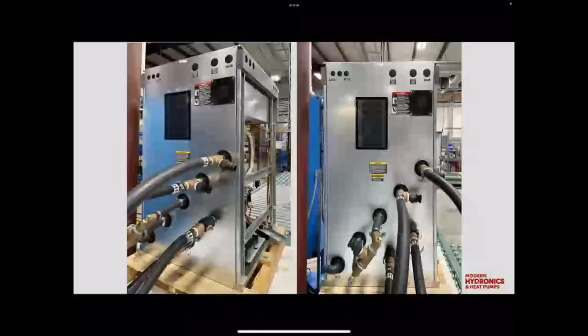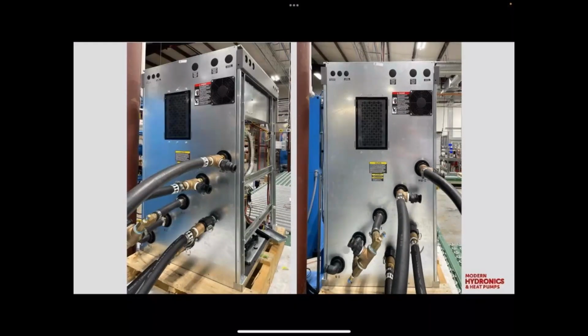So as we get in here, we're going to talk about some new stuff across the back of the unit. This is on the production line. These are actually pictures from pilot units being built. You can see here, these were getting ready for run tests. And so we have the 5 ports across the back. These 2 lower ports in the bottom left are the supply and return for the ground loop. The center port here is the common return for the load side, and then the next port up is the load out, and the very top port is the domestic hot water out.